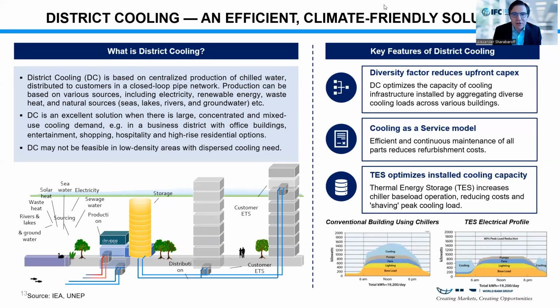District cooling requires diverse cooling load profiles of end users, so you want to avoid having users with the same profile - the more diverse and mixed it is, the better. From the sectors we've seen in developing markets, typically commercial load can be an anchor, then retail, hospitality, and residential. Residential users on their own, without any other loads, are possible but less desired.